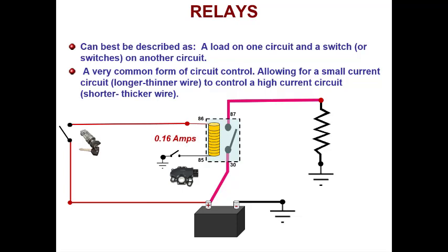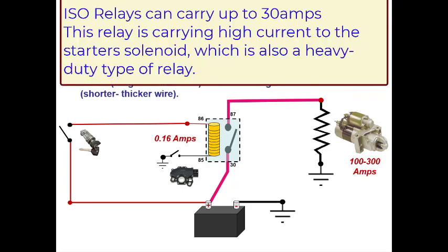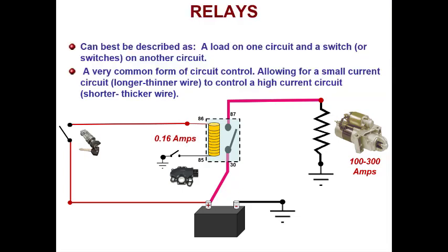When these two switches are closed, that relay has close to 78 ohms in it, which is going to allow for 160 milliamps or 0.16 amps. Because of that, we can use little teeny tiny wires to actually control this relay. The other side of the relay, pins 30 and 87, are actually carrying current capable of running a starter. So this starter is running 100 to 300 amps. When current leaves the relay at pin 87 and goes to the starter, it's actually powering an additional relay, which is on the back side of the starter, which is called a solenoid, which we'll get into later on. It's allowing current to run into that solenoid. So what we have are multiple relays all working together to perform a function.